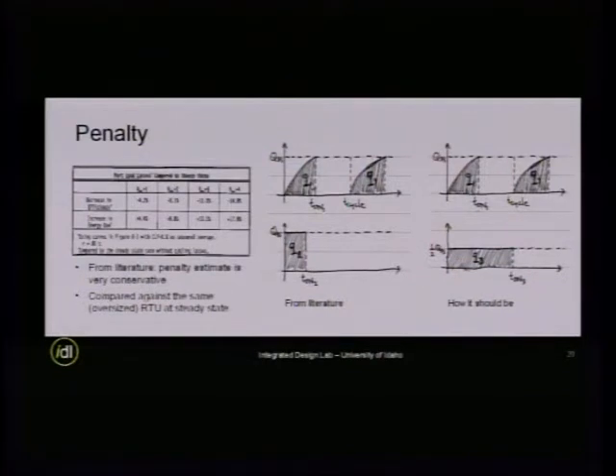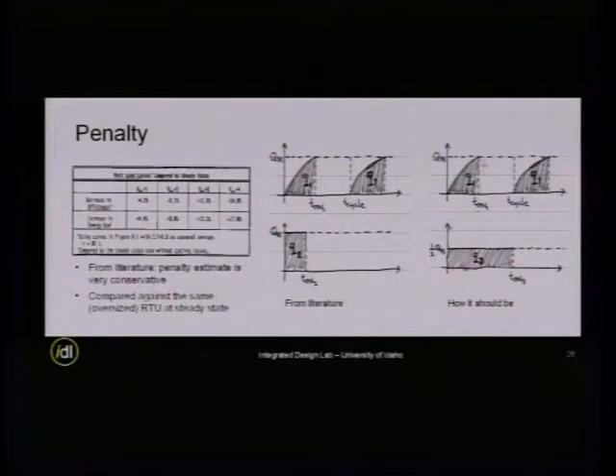But for me, it's wrong. It's at least not right. That's not entirely correct. What is exactly correct is that we want the right sized unit. To compare the penalty, you have to compare the oversized unit with the right sized unit. So the sketch will show the same oversized unit cycling on and off, but then we have to compare its performance with the right sized unit, which is probably only half of the capacity and runs over a period of time. Then the penalty we calculate is between Q3 and Q1, and I bet you it's going to be more than 17%. Or even if it is the same, let's say it's the same.